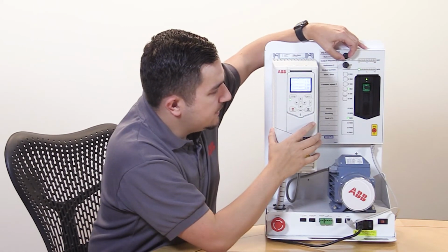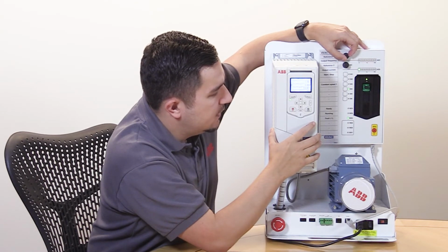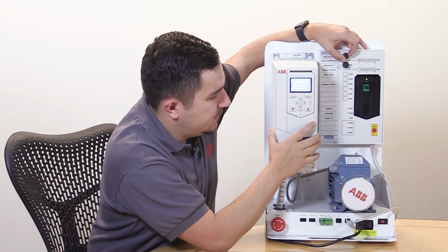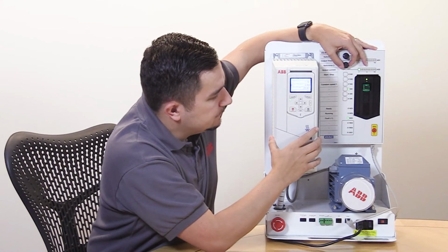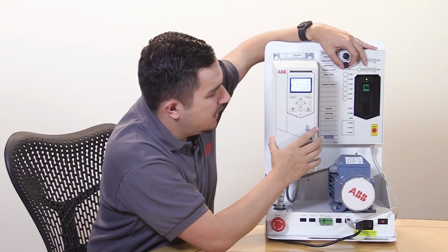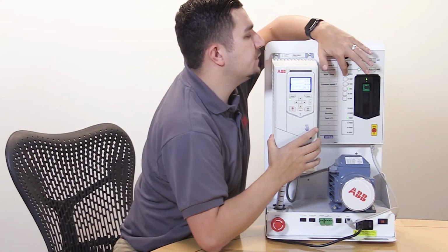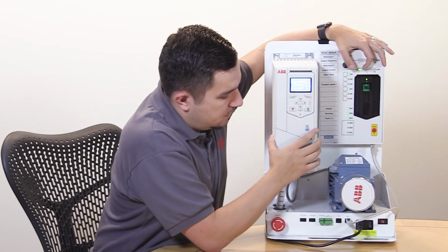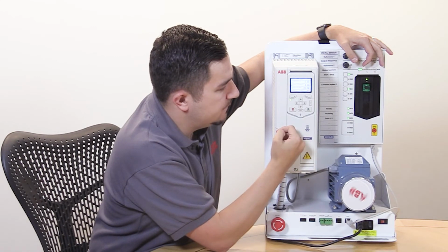So in this example, I'm going to set our PID set point, our temperature, so that the pump needs to run faster to achieve a temperature of about 21 degrees. Our feedback's going to be really low at the moment, so I'm just going to start to increase that gradually, so we can start to see a value at least. And then once I get the digital input to start, we can see now that the feedback's saying it's at 4 degrees.